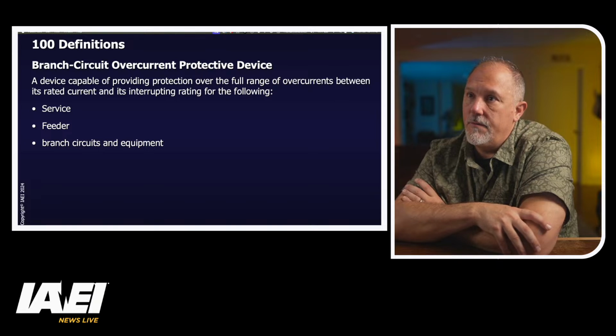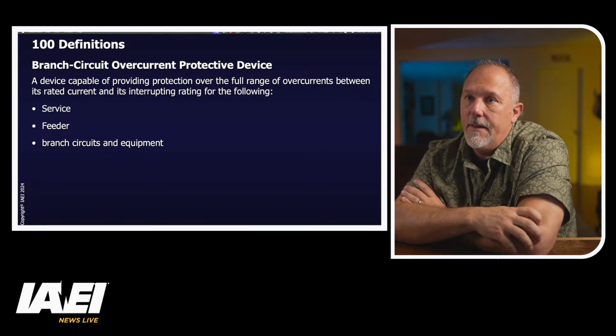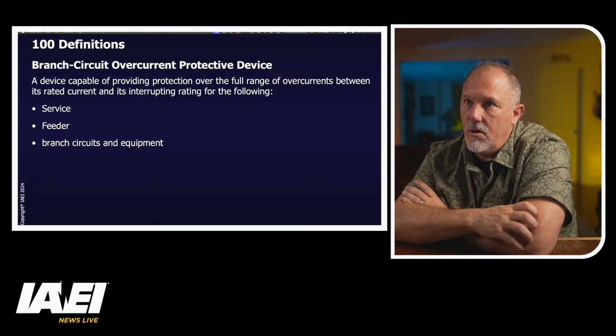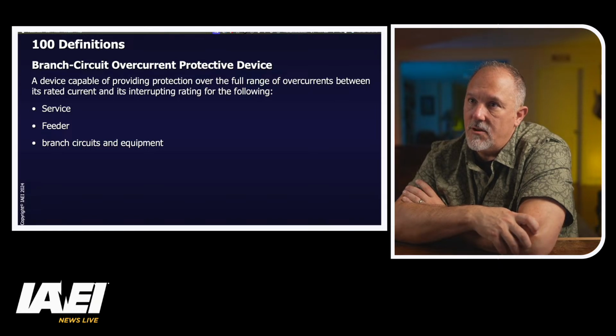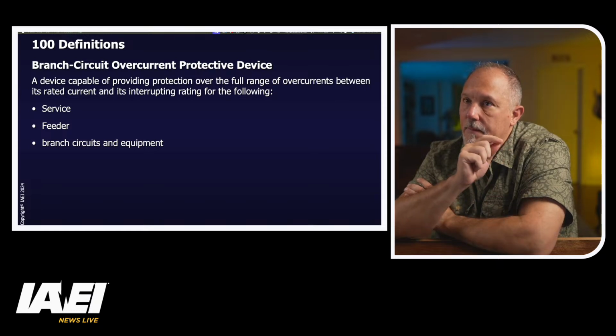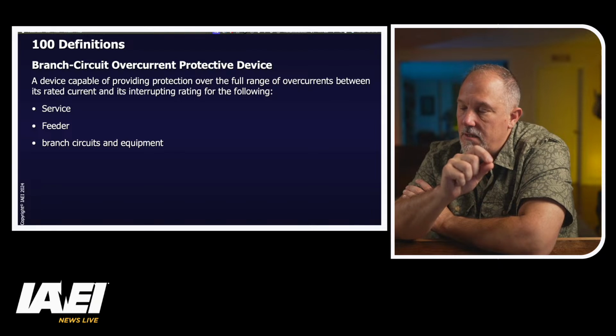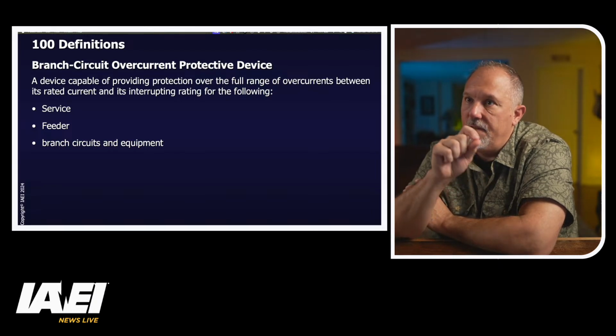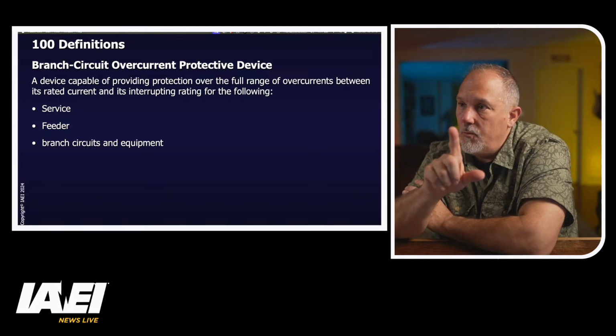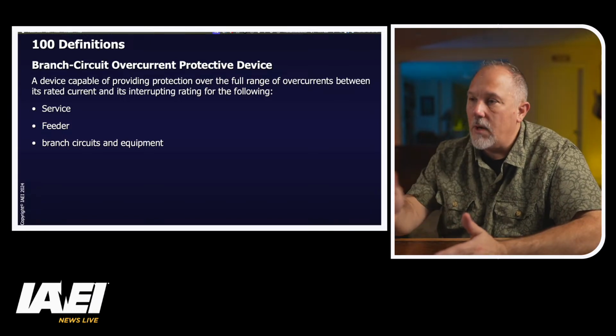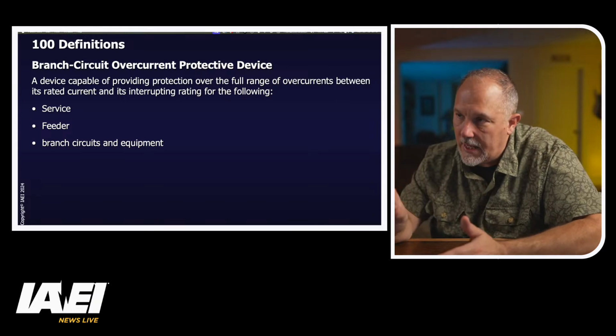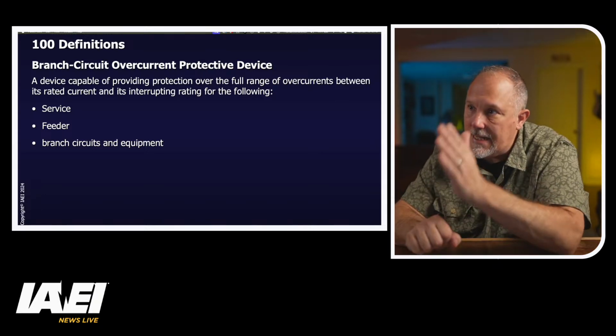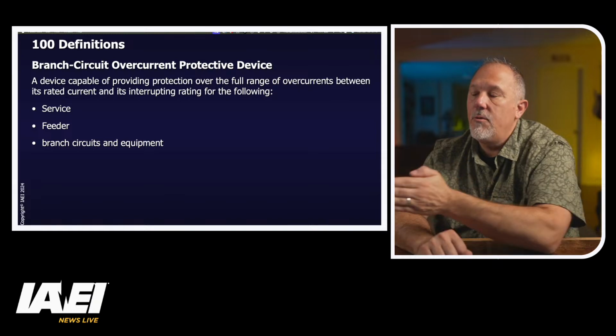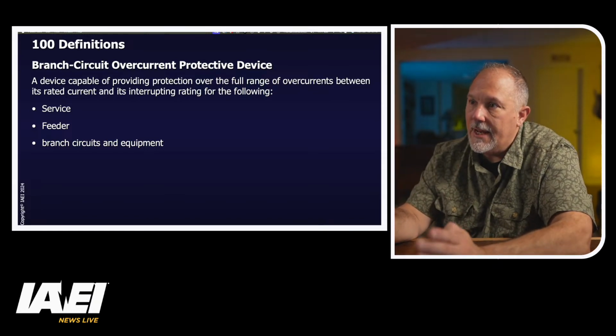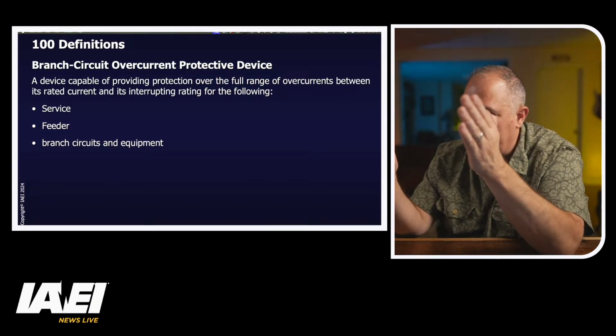Definitions of terms and terminology are critical to our success in this picture. A device capable of providing protection over the full range of overcurrents between its rated current and its interrupting rating for the following. So it's a device that protects for the full range of overcurrents. And it says between its rating. So if I have a 20 amp circuit breaker, the rating of a 20 amp circuit breaker is 20 amps. So this device has to provide protection from 20 amps through its interrupting rating. And if it's a 22,000 amp interrupting rating, it has to provide protection from 20 amps to 22,000 amps.